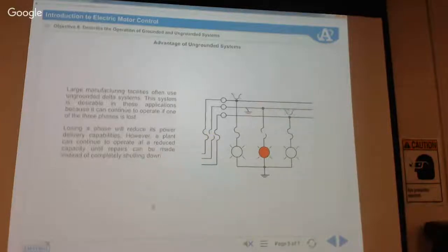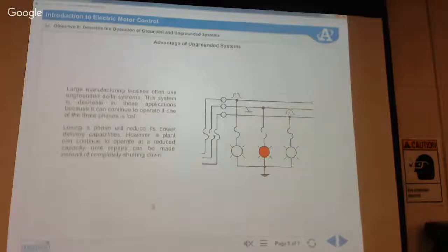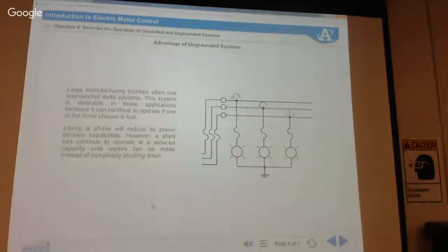So this talks about large manufacturing facilities often using ungrounded delta systems. This system is desirable in these applications because it can continue to operate if one of the phases is lost. However, most plants are running close to their max potential, so they're going to shut down if they lose a phase regardless. The rest aren't going to be able to keep up. But your book says otherwise, so.